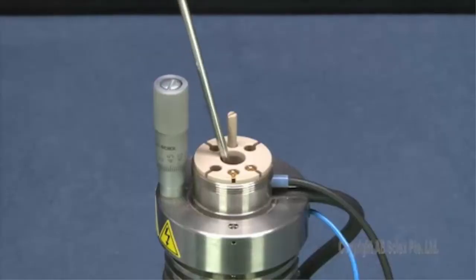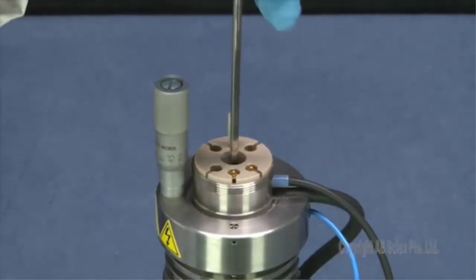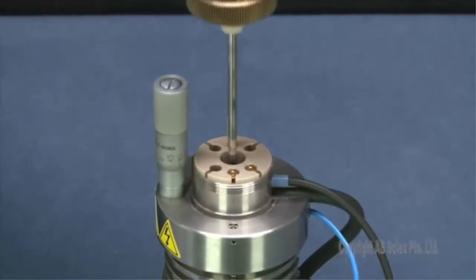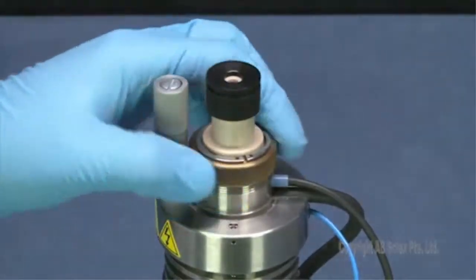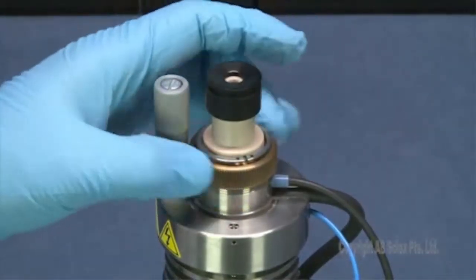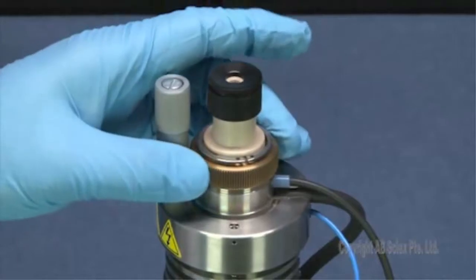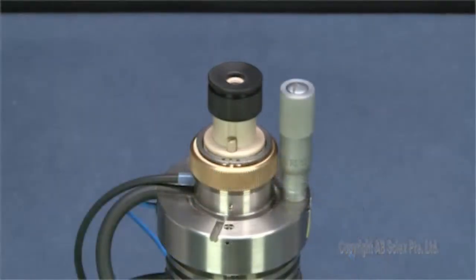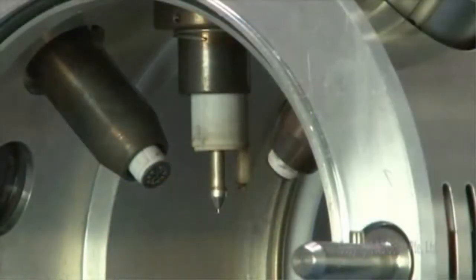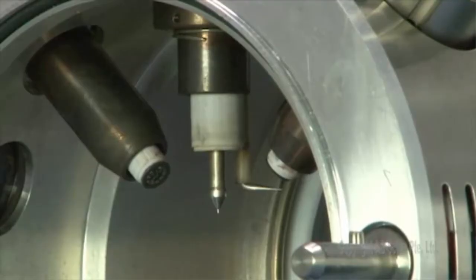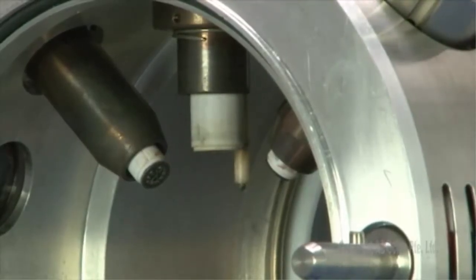Insert the probe into the tower, taking care not to allow the tip of the probe to touch any part of the ion source housing. Push down the brass retaining nut to engage its thread with the ion source housing thread and tighten the nut. If needed, adjust the corona discharge needle to the proper position for that probe. For the ESI, the needle position should be 180 degrees away from the instrument orifice. For APCI, the needle should be facing the instrument orifice.